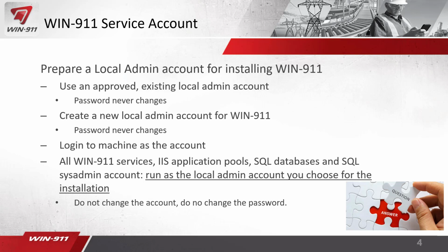Okay, so what happens is you install it as account A and you want to change it to account B. Now you have multiple services that you have to change manually, multiple IIS application pools that you have to change manually, and you have to go into the SQL database as the original account that has permissions, because remember, this was made the sysadmin account. So you have to log in as original account A and add account B there to make that also a sysadmin and own all of the databases for Win911.